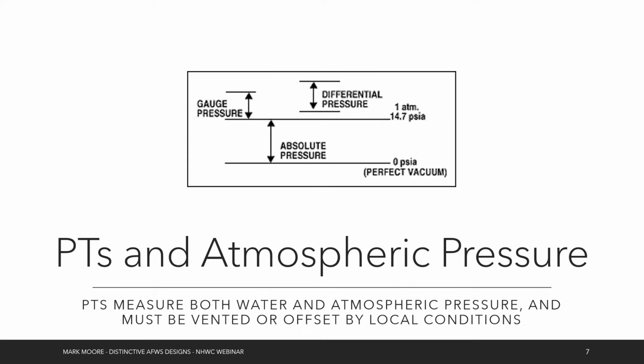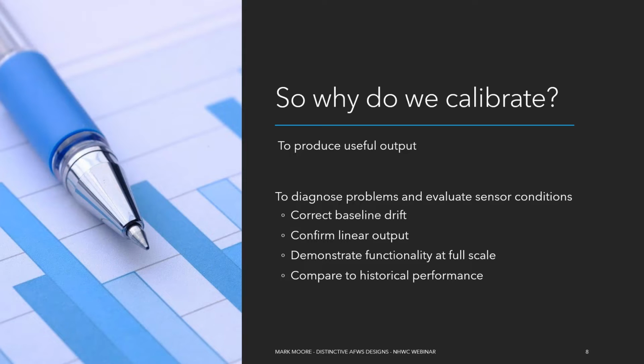But this isn't a talk about pressure transducers, as I promised, so I'm not really going to harp too much more about keeping your desiccant fresh. This is a talk about calibration. So why do we calibrate? Well, at the end of the day, we calibrate to produce a useful output, because a lot of these sensors aren't actually saying it's 10 feet of water. They might put out something like 2 volts or 15 milliamps or 0.18 psi. What we care about is the depth of the water with pressure transducers. And what we care about with tipping buckets is the inches of rain. Just saying that it tipped once doesn't mean anything unless we know how many inches are in each tip.